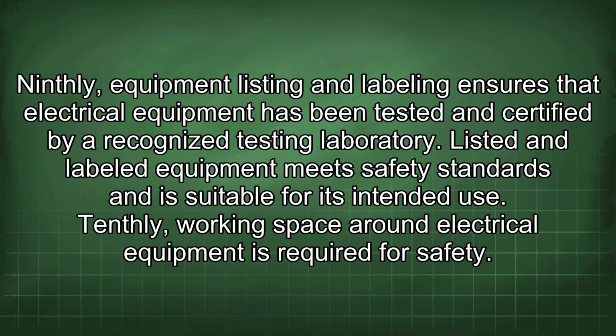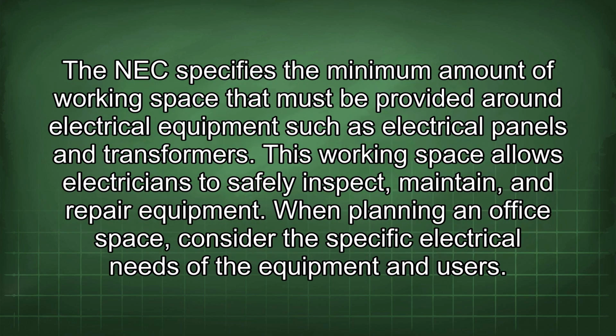Ninthly, equipment listing and labeling ensures that electrical equipment has been tested and certified by a recognized testing laboratory. Listed and labeled equipment meets safety standards and is suitable for its intended use. Tenthly, working space around electrical equipment is required for safety. The NEC specifies the minimum amount of working space that must be provided around electrical equipment such as electrical panels and transformers.